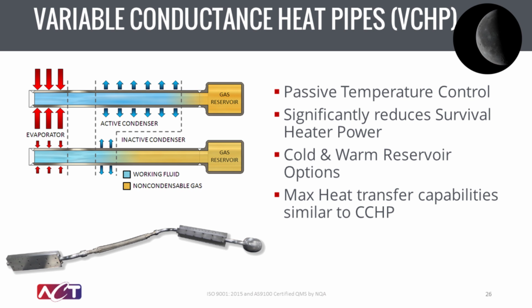So the gas reservoir on the end contains a non-condensable gas, and as the temperatures change and the heat load changes, so you can see on the top image, the heat going into the evaporator, those are the big arrows, that's indicating that it's on and a lot of power. The blue is the two-phase working fluid that allows the variable conductance heat pipe to be operating in the high conductance mode where it's on. And then as the temperature and the heat load reduce, that's the little arrows on the image on the left-hand side into the evaporator, that two-phase working fluid retracts. The non-condensable gas comes out of the gas reservoir and blocks off a portion of that condenser to turn down the amount of heat that's then being rejected. And what that allows you to do is to maintain a steady evaporator temperature.